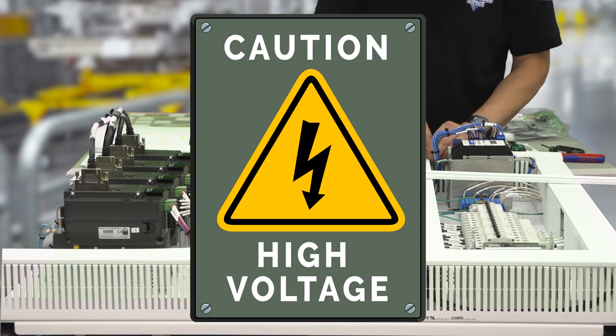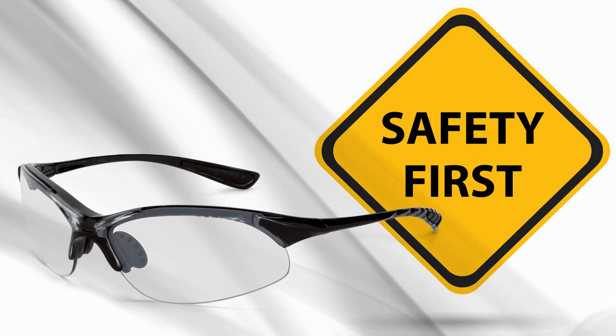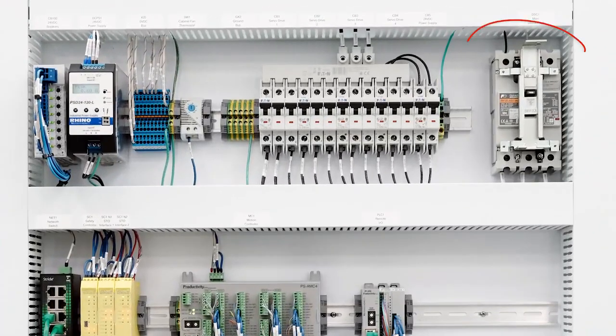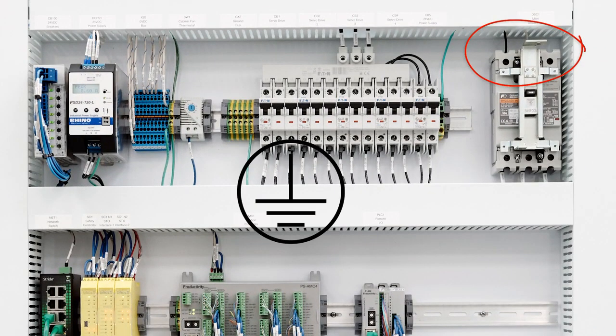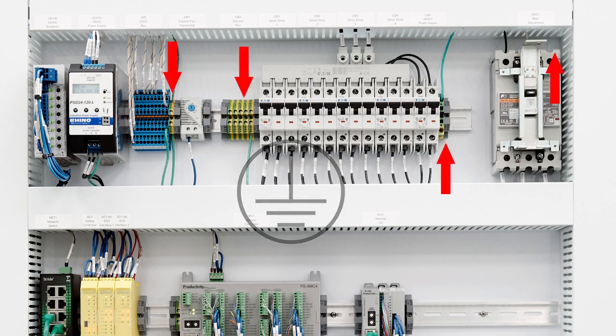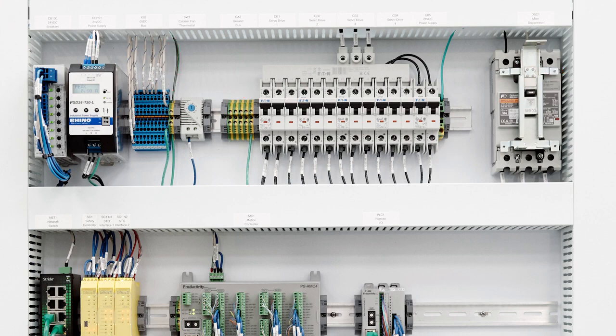Be aware that panel build may involve higher voltages that can be dangerous, so wear safety glasses and other required PPE safety gear and follow all local laws and codes to ensure your safety. Start by attaching the power supply and ground. Do not skip your ground, particularly during testing. The ground wire is there to protect you and the wiring by providing a safe path for errant power away from the panel. If you don't install a safe return path, you may become the return path.